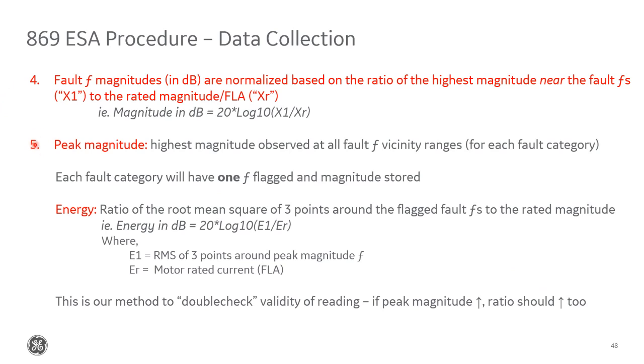Then in step five, we register for each of the three fault categories what frequency has the highest value, and then we store that as the peak magnitude value for that category. So in total, we'll have three peak magnitude values stored. And then just as a double checking mechanism, we also do what we call an energy calculation, which we take as the RMS of three values near the peak fault frequency, the ratio of that to the FLA, and then the log magnitude. The idea with this is that if the peak magnitude value increases, then this associated energy value should also increase. If there's no correlation, then something's probably wrong.